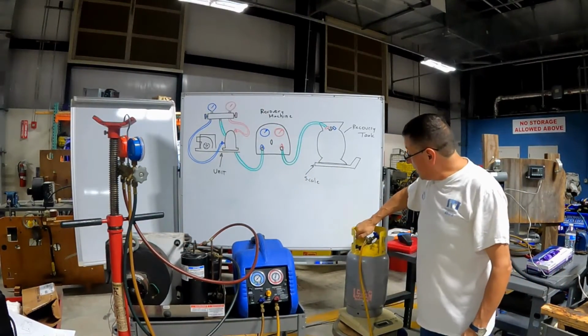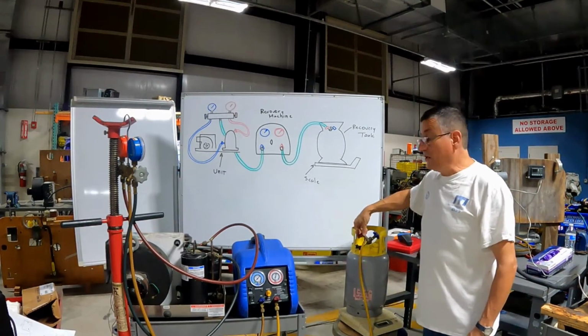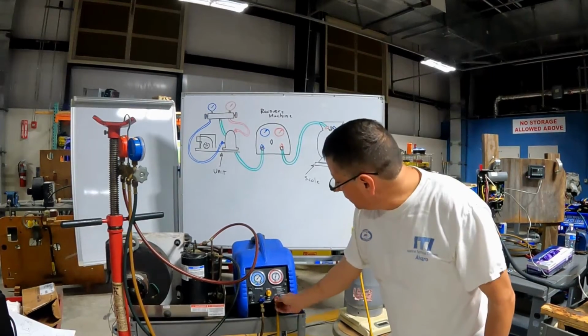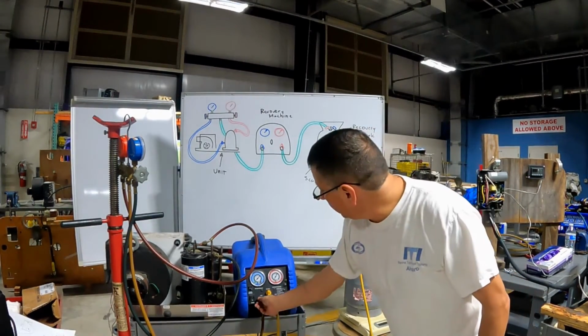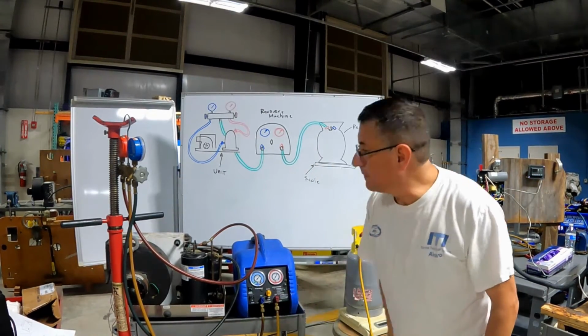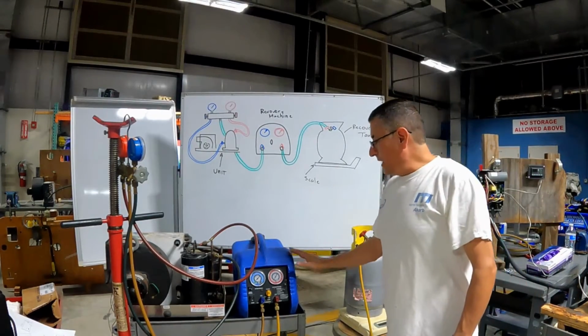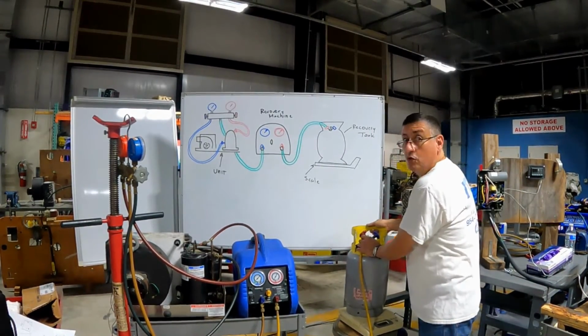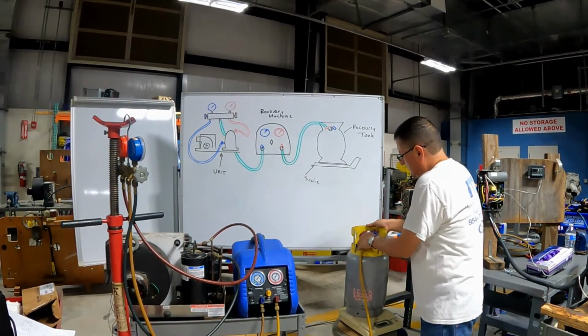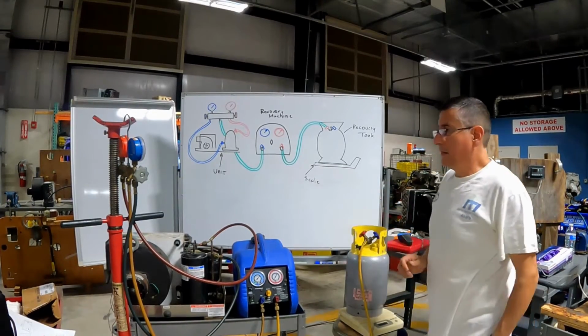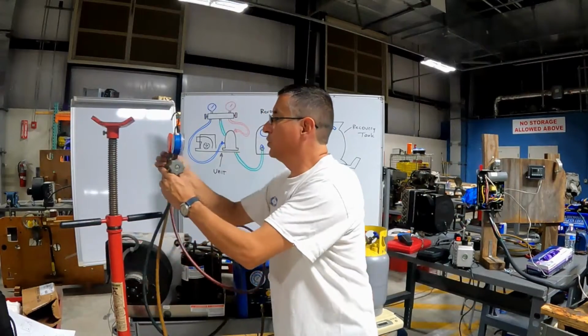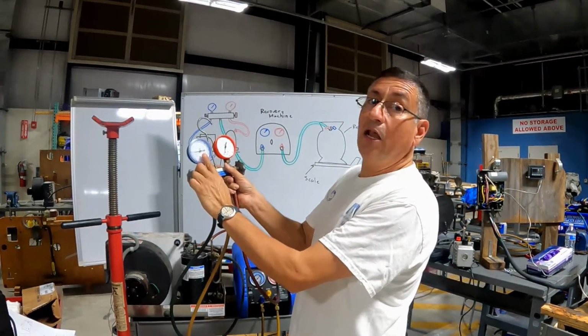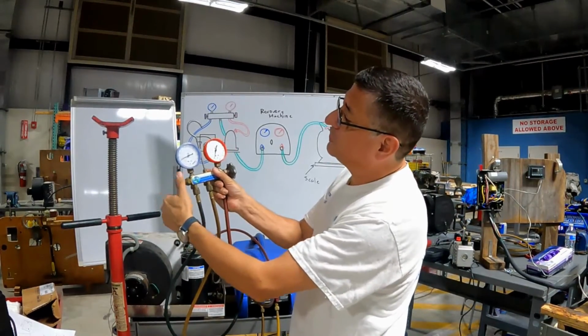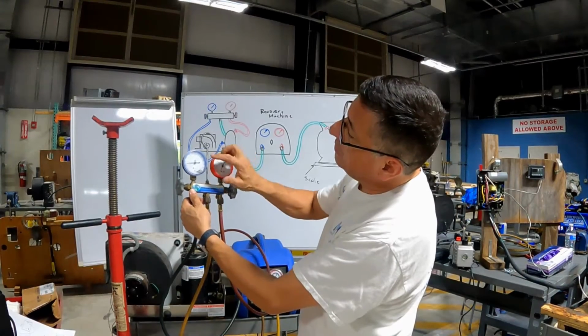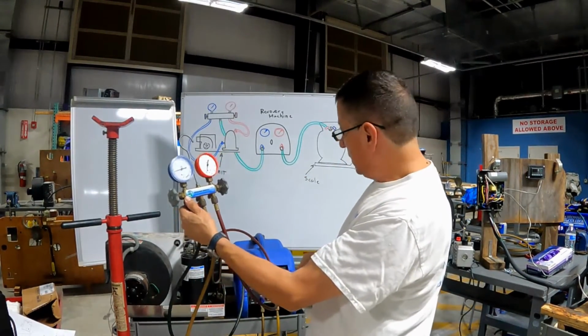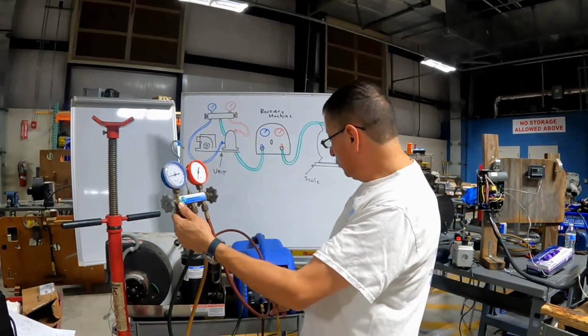Right now we are going to open the valve of the cylinder, and we are going to open the discharge valve of the equipment, and we are going to open this one right now. Open, and we are going to release a little pressure over there to bleed the air, and you tighten again. And right now we are going to open the low pressure side, and we are going to verify we have 18 psi of pressure. And right now we are going to start the system to suction.